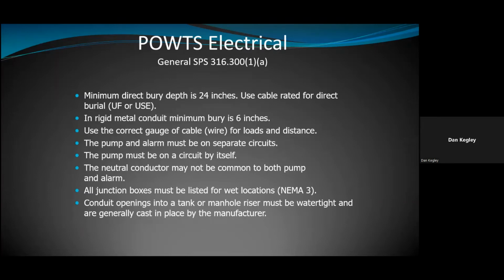As we can see here, 316.300, 1.A covers a little bit about the electrical wiring of the POWTS systems. The minimum burial depth listed here is 24 inches using cable rated for direct burial. So even your low voltage cabling has to be listed for direct burial. I find that a lot of times people use Cat 6 cable or some other two wire, three wire phone cable. That's just a standard cable, and it should really be a direct burial cable. It'll say right on the outside of the cabling that it's to be installed for direct burial. Otherwise it breaks down over time underground, and you get either faults or it doesn't work altogether.